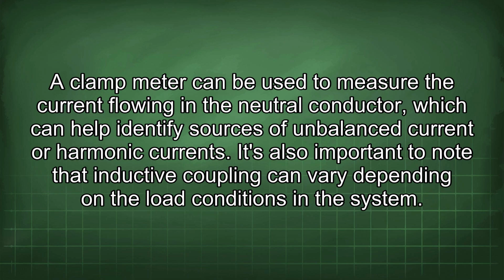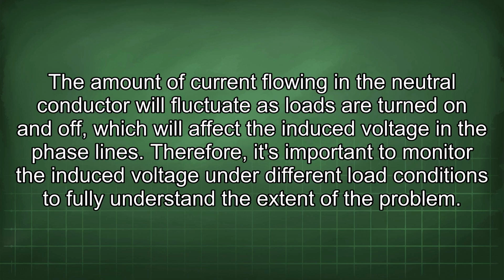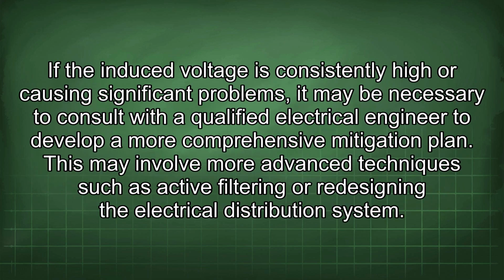It's also important to note that inductive coupling can vary depending on the load conditions in the system. The amount of current flowing in the neutral conductor will fluctuate as loads are turned on and off, which will affect the induced voltage in the phase lines. Therefore, it's important to monitor the induced voltage under different load conditions to fully understand the extent of the problem. If the induced voltage is consistently high or causing significant problems, it may be necessary to consult with a qualified electrical engineer to develop a more comprehensive mitigation plan. This may involve more advanced techniques such as active filtering or redesigning the electrical distribution system.